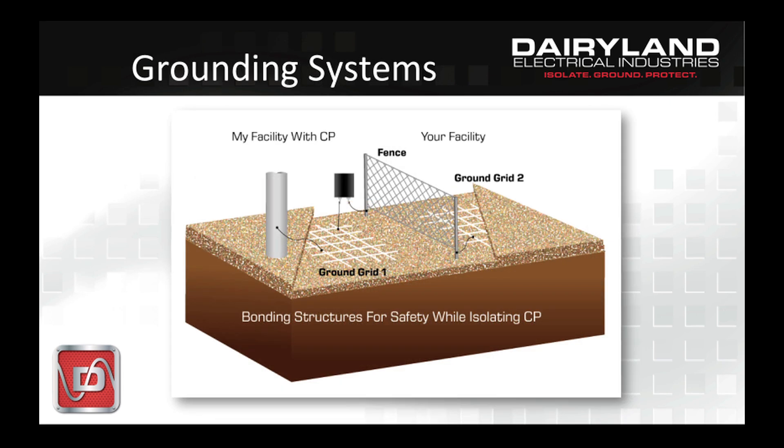Your grounding system and a neighboring grounding system may not be bonded together. You might ask why worry since each facility has a grounding system — but what if you could contact both systems at once and they weren't at the same voltage? During a lightning event or an AC fault, one facility could be affected but not the other, leading to a voltage difference between the two. You could contact these grounding systems by touching objects bonded to ground, such as facility piping, a fence, support structures, or buildings. You could bond the grounding systems and fence together with a suitable wire if no CP system is involved, but sometimes CP is tied into the grounding of a facility and must be kept separate from foreign grounding systems via a decoupler.